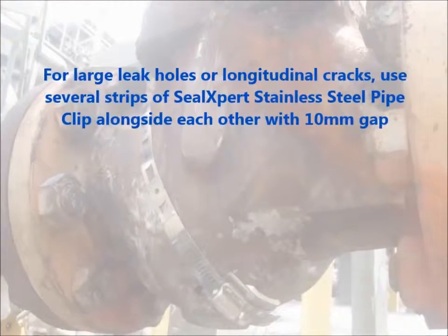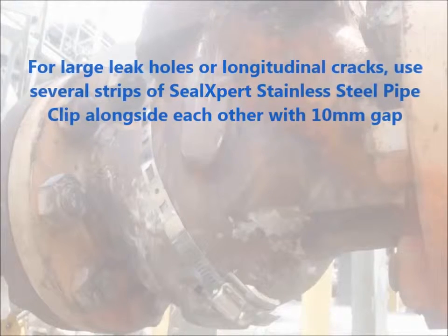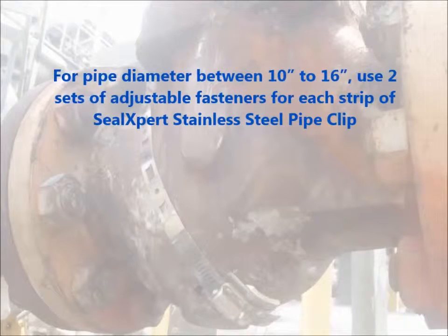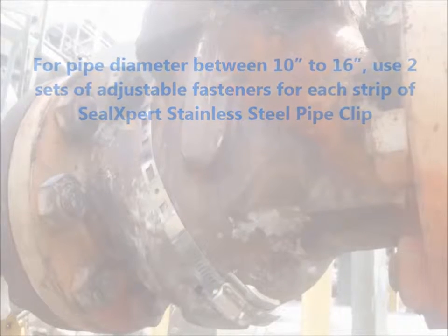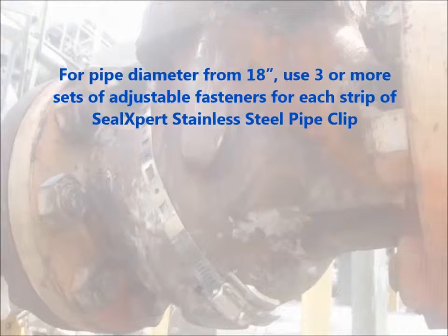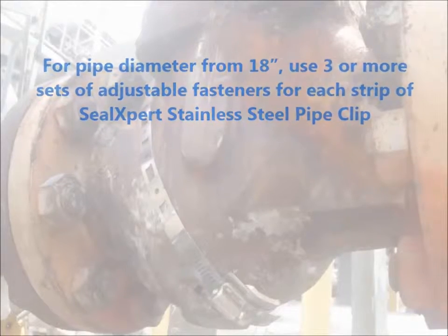For large leak holes or longitudinal cracks, use several strips of SealXpert Stainless Steel Pipe Clip alongside each other with 10 millimeter gaps. For pipe diameters between 10 inch to 16 inch, use two sets of adjustable fasteners for each strip. For pipe diameters greater than 18 inch, use three or more sets of adjustable fasteners for each strip.